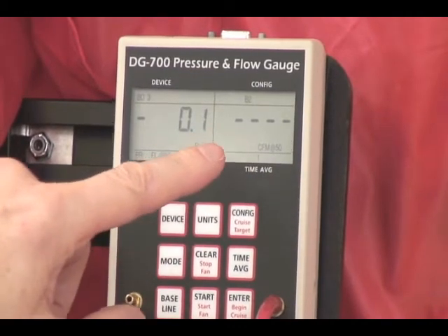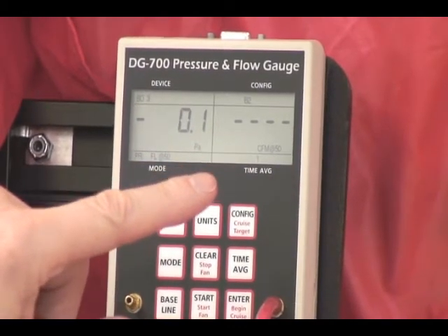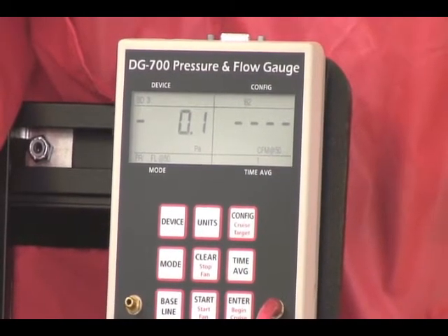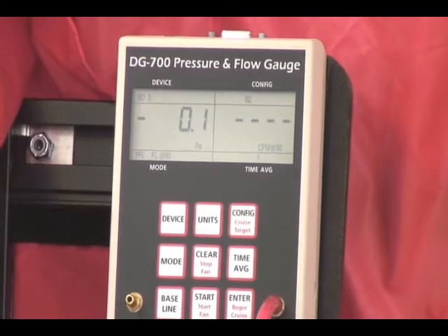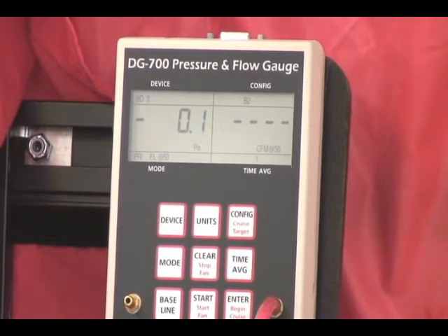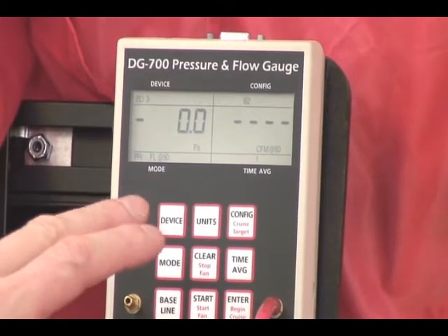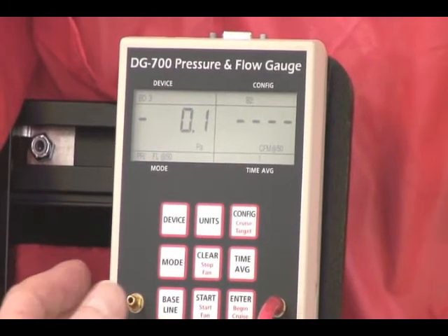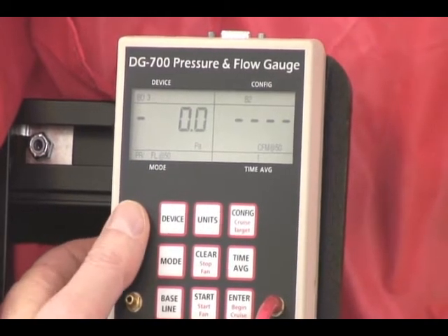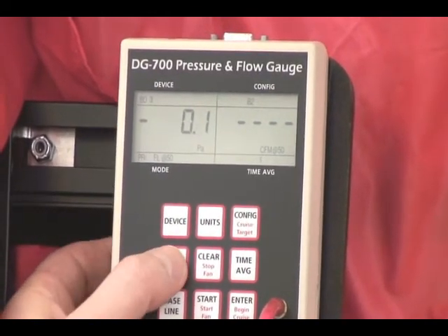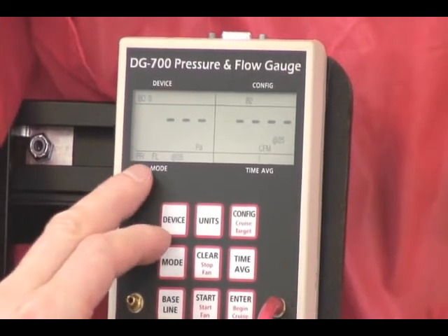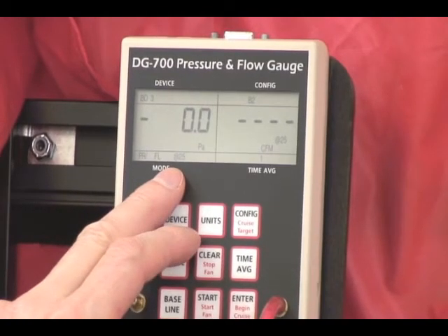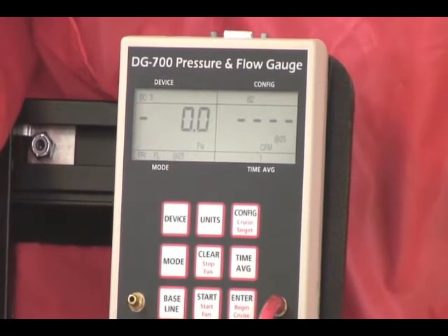This CFM at 50 pascals is an extrapolation mode that we'll show you later, where you don't have to achieve the exact test pressure. You can get an approximate test pressure, say 45 to 55 if you're trying to achieve 50, and this will mathematically extrapolate it to 50 pascals as if you were at 50 pascals. This is very, very commonly used with blower doors. The next mode, however, which is pressure flow at 25 pascals, is much more commonly used in ducts, and we won't be going into it in this section.